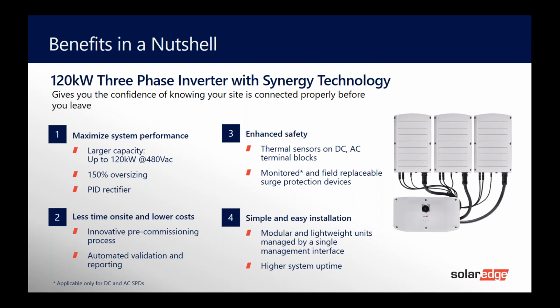Also the oversizing. This inverter coming out of the box now has the ability to go to 150% oversizing without any waivers. Now I should stop there and put a caveat: even the existing inverters on the 480 side, anything above 30 kilowatt 480 SolarEdge inverter, is the same thing. You could go to 150%, you no longer require a waiver. And on the 208 side, anything above the 14.4 kilowatt, you can go to 150% with no waiver.